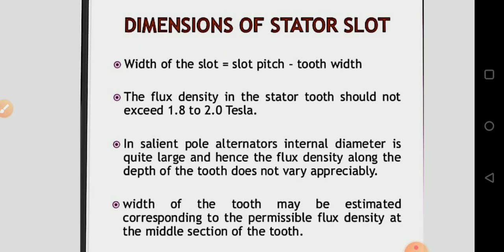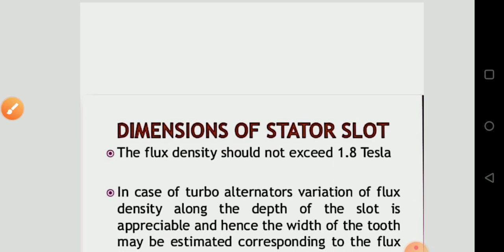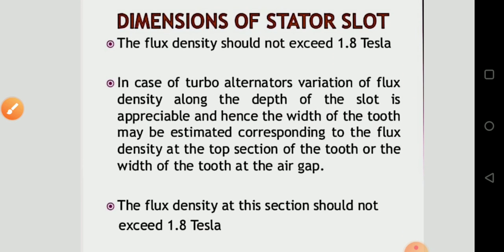Next, the tooth width is estimated at the middle section of the tooth. For estimating the width of the tooth, we calculate the width along the middle section of the tooth. The flux density should not exceed 1.8 Tesla.